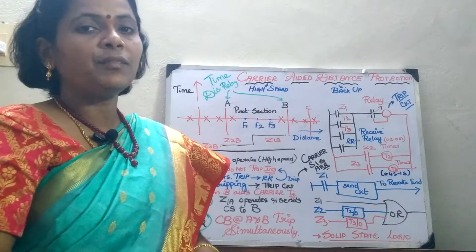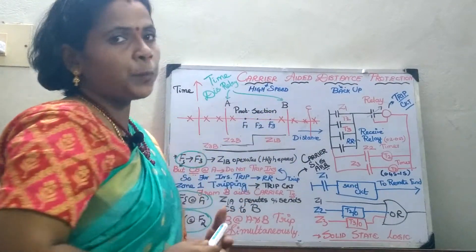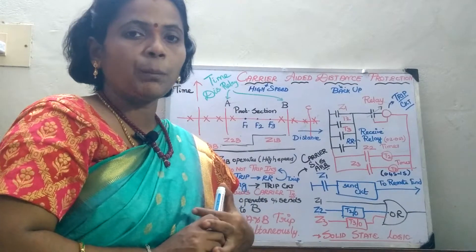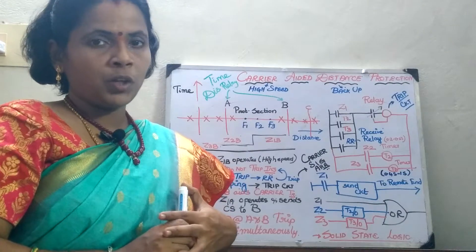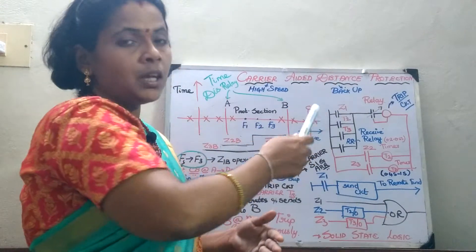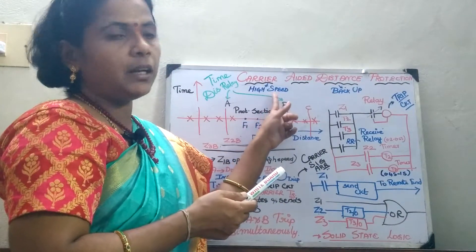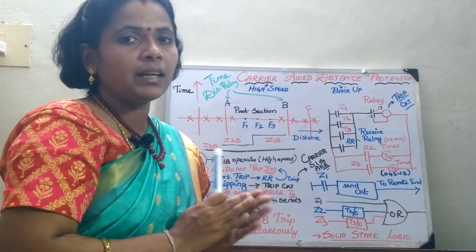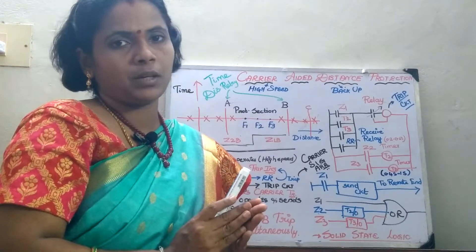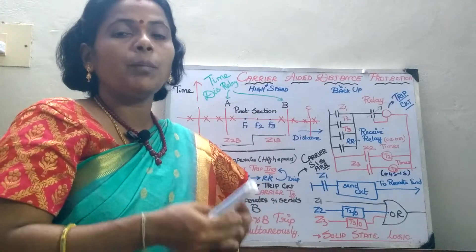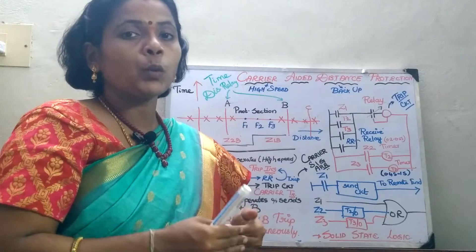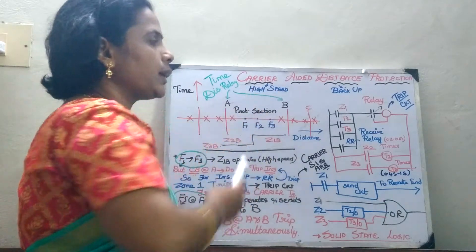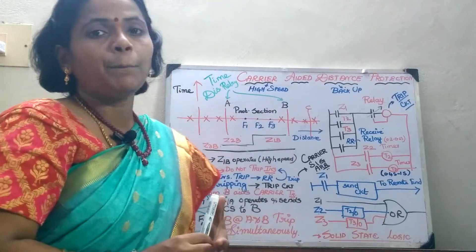The advantage of carrier protection is high speed — it offers unit protection. Whereas distance protection helps in backup protection; it is a non-unit protection. The disadvantage of carrier aided protection is that it can only be used for primary protection, but in reality both primary and backup protection are required. So we are going to combine both schemes to attain better benefit: high speed is offered by carrier protection and backup protection is offered by distance protection.